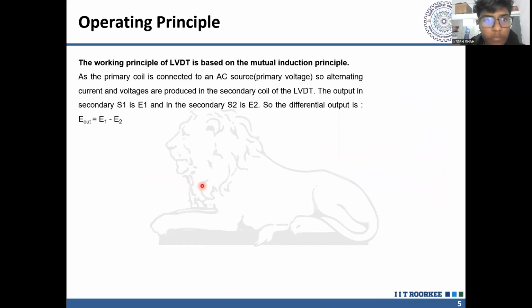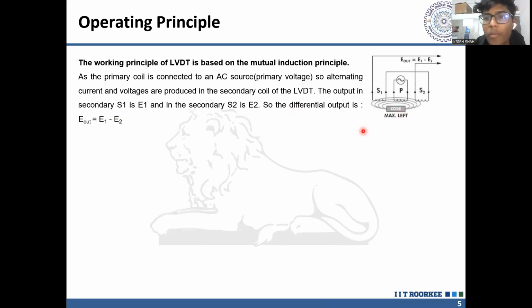Let's get into the operating principle, how the motion of the core gives us a differential output. The working principle of LVDT is based on mutual induction. As we said, we provide excitation voltage to the primary winding, which induces flux, and that is transferred through the moving core to the secondary windings, so there is mutual induction between the primary and the secondary windings. What we measure is the difference between the induced EMF in secondary winding S1 and the induced EMF in secondary winding S2. E output is E1 minus E2. Now we have three different cases of what can happen.